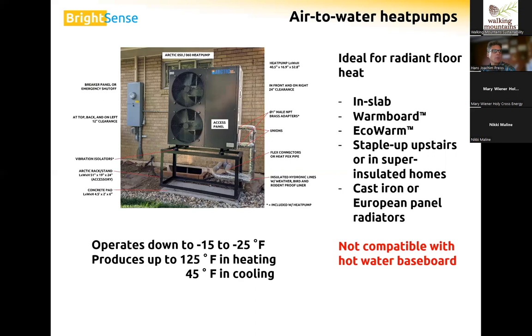We can produce up to 125 degrees Fahrenheit water in heating mode, and that makes the heat pump a really, really good tool for any type of radiant. Typical in-slab radiant, either slab on grade, like a basement slab, or an elevated slab, lightweight or regular concrete slab, and then products like Warmboard, EcoWarm also work extremely well. I'm going to have another slide on that coming up. Staple up also works under certain circumstances in really well insulated homes.